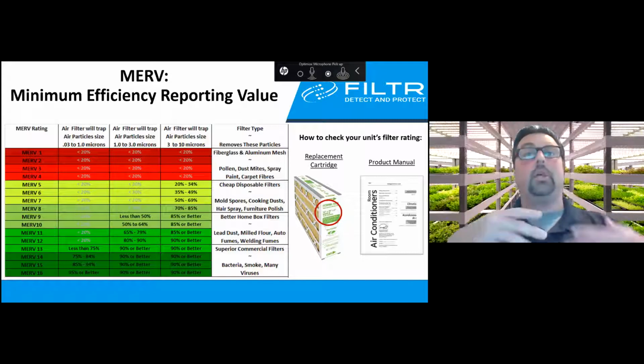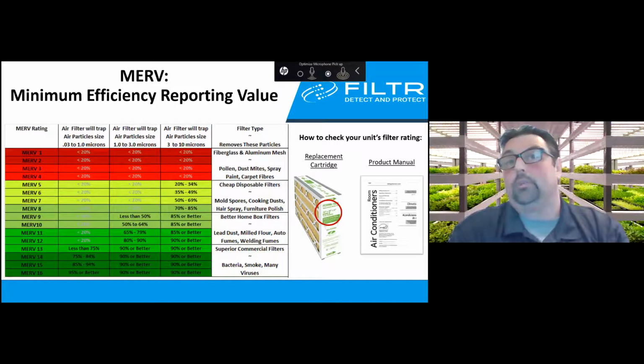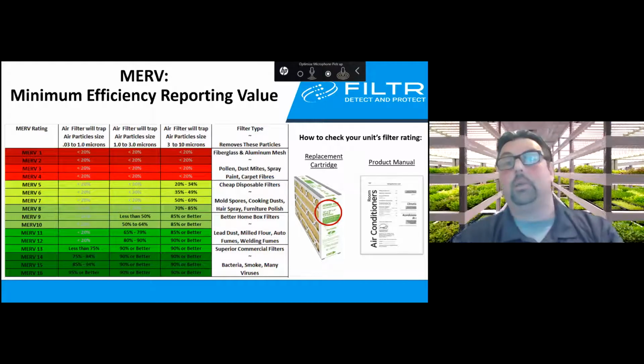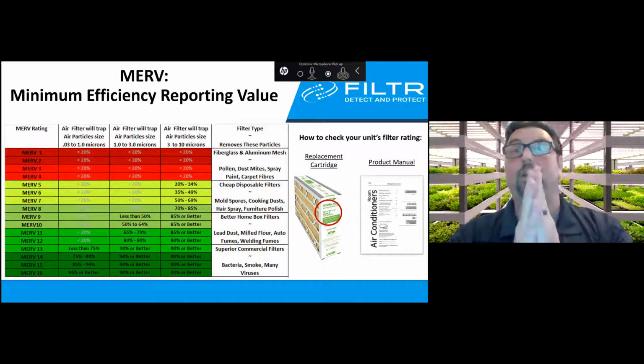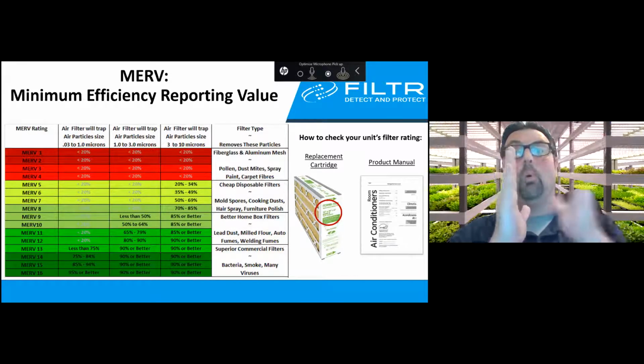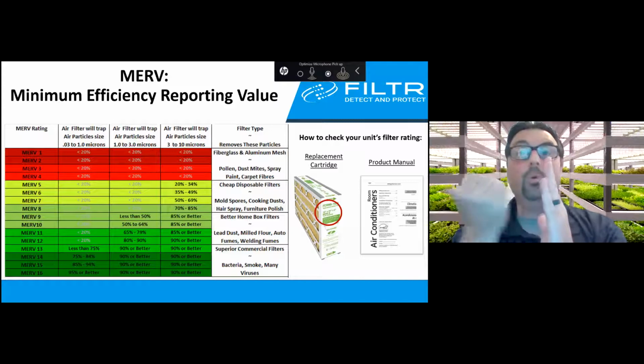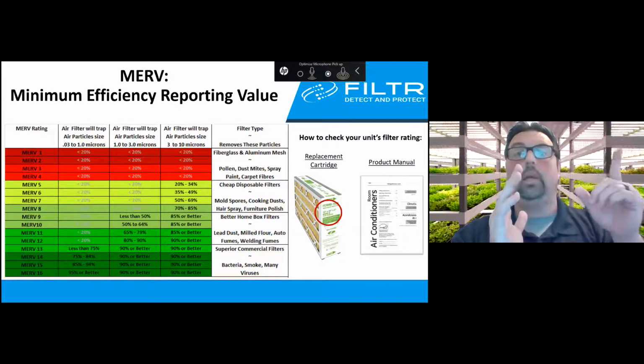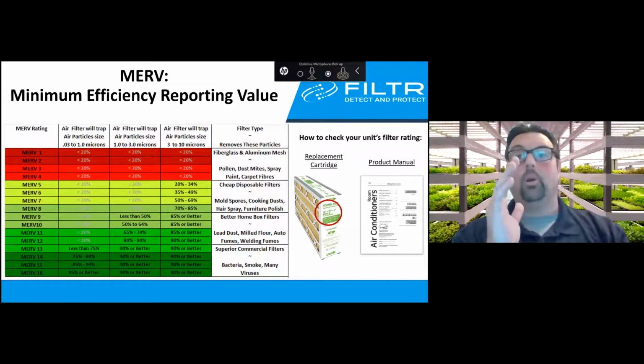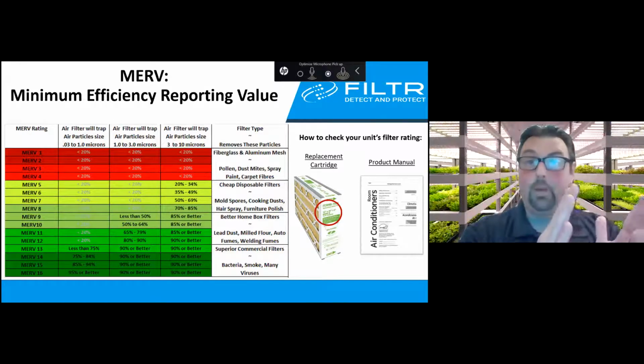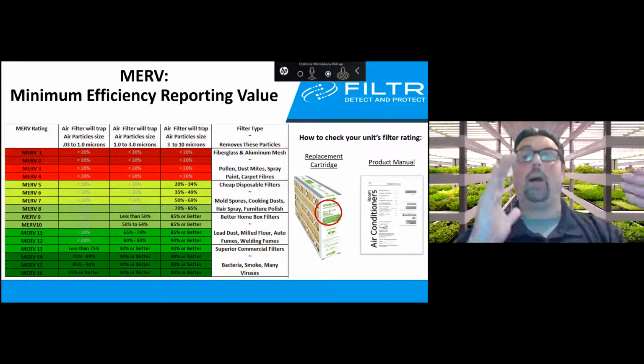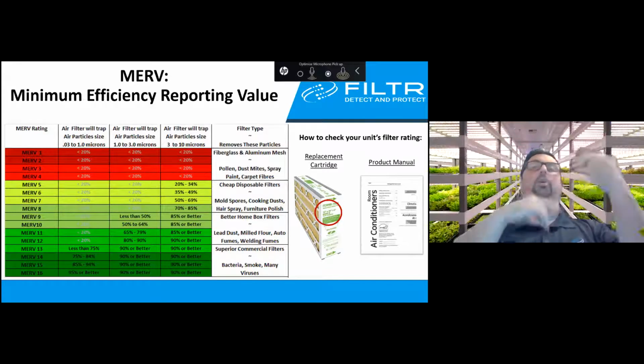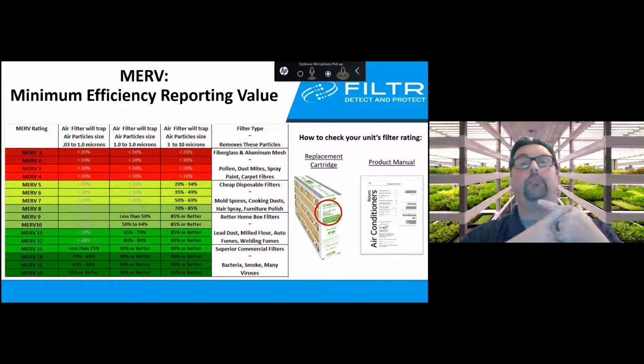Because here's what's happening: you're saying, okay, we're using MERV 8 filters, cool, let's throw some 13s in there and see what it does. But here's the problem: it's a thicker filter media, so you're going to have to produce more air pressure to get through that filter. If your unit is not producing enough air pressure, it's going to back pressure. If it's having to constantly force air through, your unit is constantly running, which will affect the life cycle of your HVAC in general.